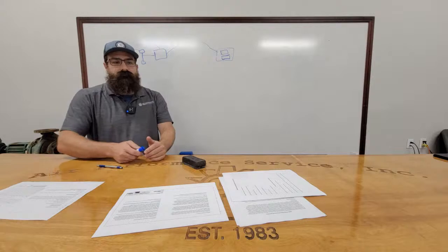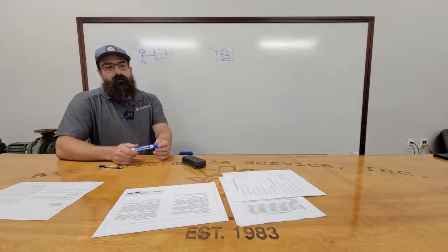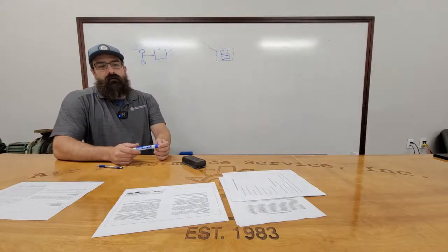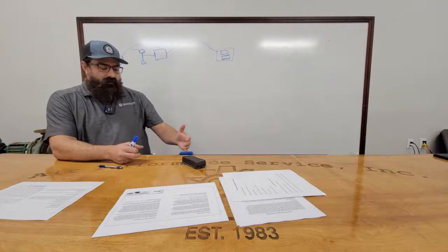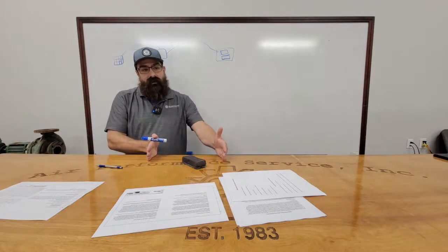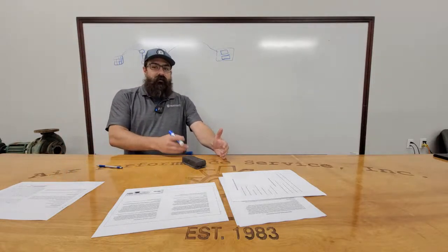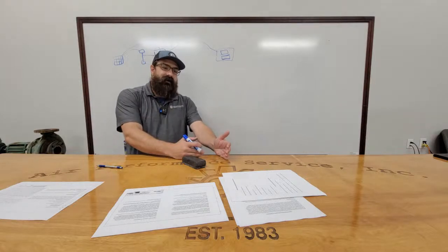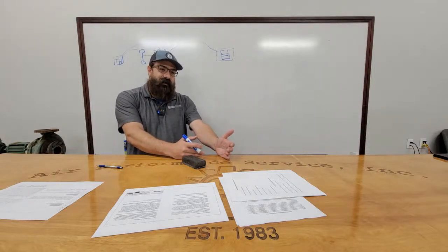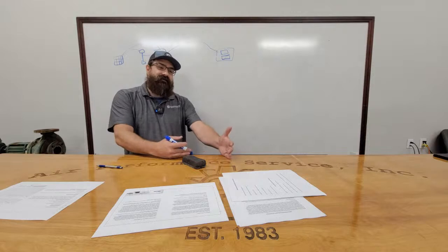Obviously, we're not going to go into super long detail, but is there a couple short pros and cons to each? There's not really. They all equate to the same thing, right? Because if you think about it, whether you're averaging space temperatures, okay, and you know, hey, I want my building to come on at 85 degrees, well, you're going to have an 85 degree unoccupied set point on all those boxes anyway. So you can do an average at that point.